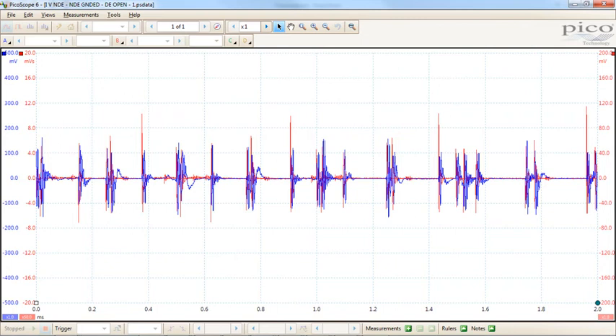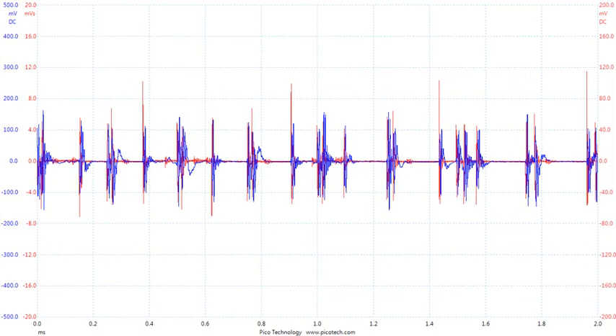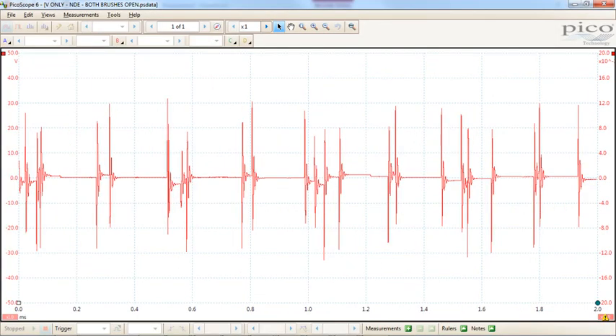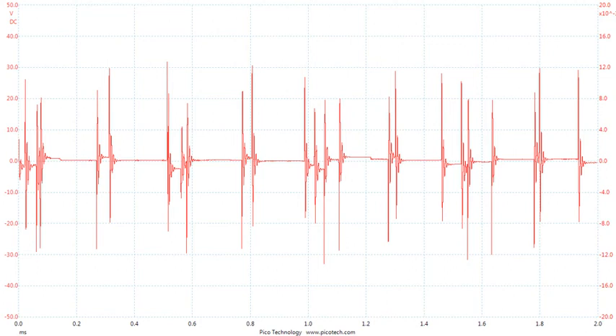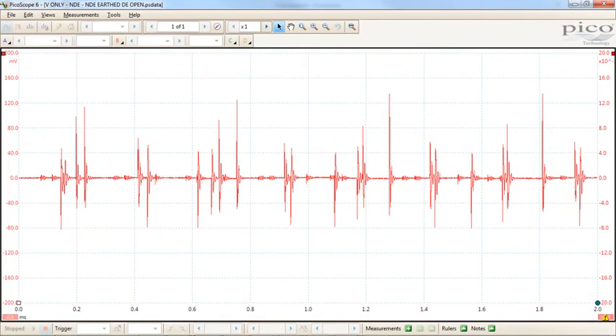Then we put one brush down, and this is the microfiber brush. So when people ask how effective the brushes are, look at that. You've got 30 volts there. Then that's just zoomed in. Maybe you can just see it better. You'll see what I mean about the common mode voltage there. Then this is with the one brush earthed, the non-drive end earthed. Look at what the voltage has dropped to, 120 millivolts.